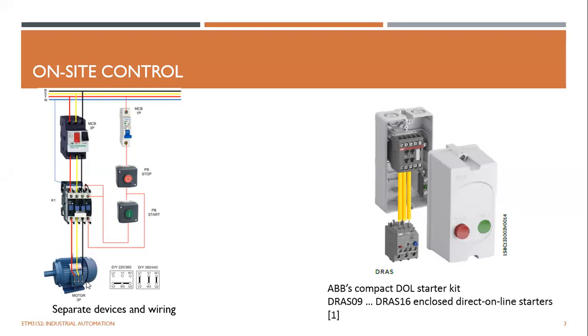And the motor can be connected in either of two configurations. If this is a 6-terminal box here, you can connect it as a star when you short circuit the 3 terminals, and when you want to connect it as a delta, this is the configuration. I will discuss them later. And this is how a local control looks. You can see this is an ABB compact DOL starter kit. So there's a start button and a stop button, a main circuit breaker, and after that this is the contactor.